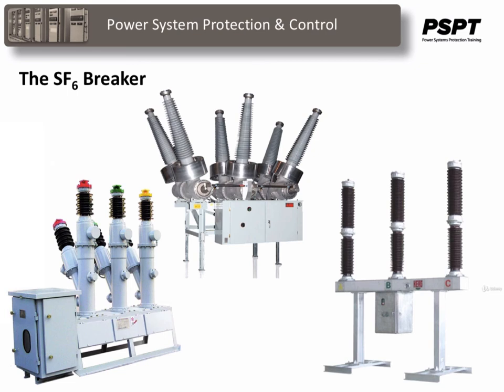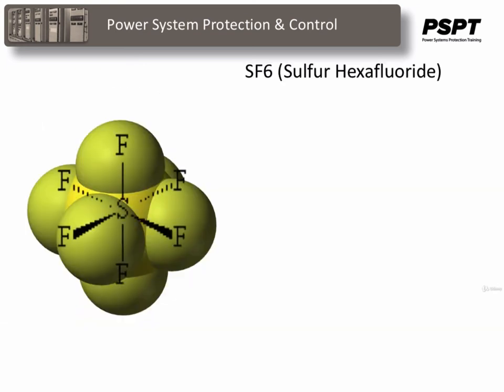Now let's take a quick look at the SF6 breaker. Sulfur hexafluoride, or SF6, is an excellent gaseous dielectric for high voltage power applications. It has been used extensively in high voltage circuit breakers and other switchgears employed by the power industry. It is also used in GIS equipment, or gas insulated power distribution substations and gas insulated transmission lines, etc.